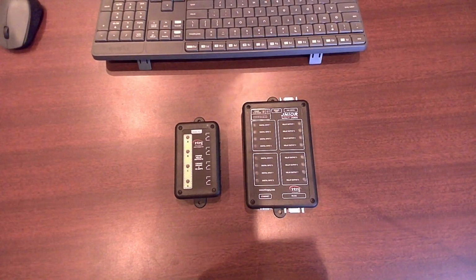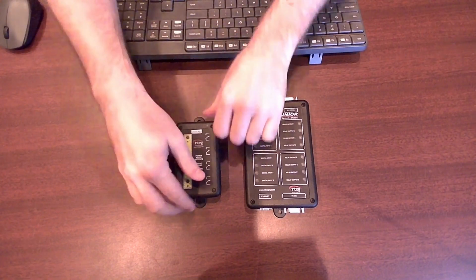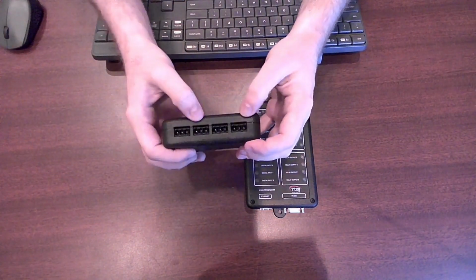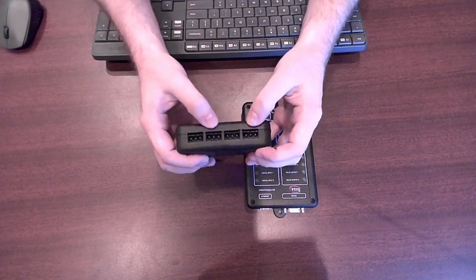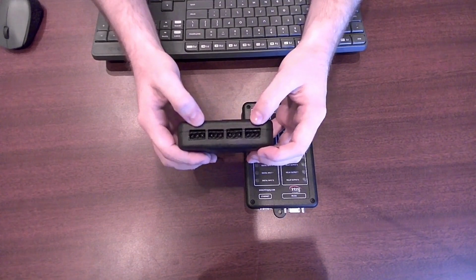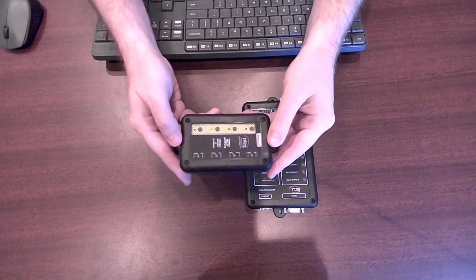The first expansion module we are going to review is the 4 relay output module. This expansion module adds 4 output relays capable of low or high voltages up to 120 to 240 volts AC at 10 amps. This expansion module is a great way to add additional outputs to your setup without needing an additional JNIOR. Looking at the outputs of this expansion module, you will see that each output has 3 pins. That is because you can wire them to be normally open or normally closed.